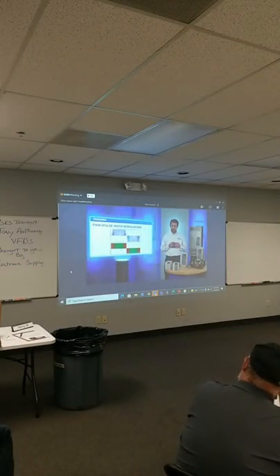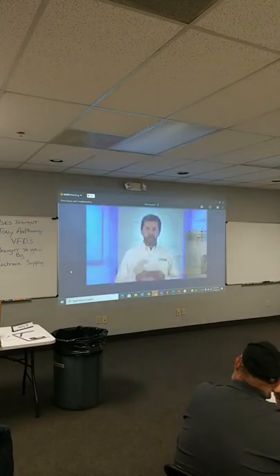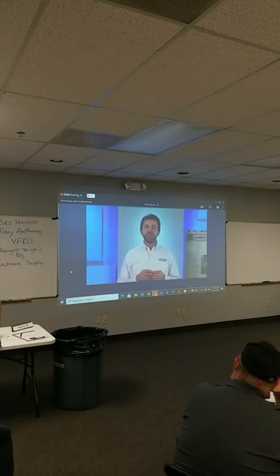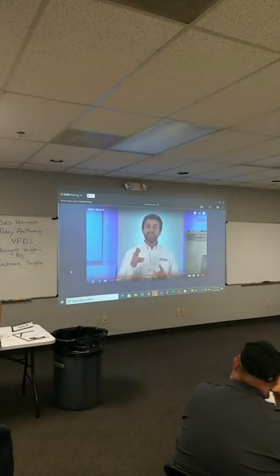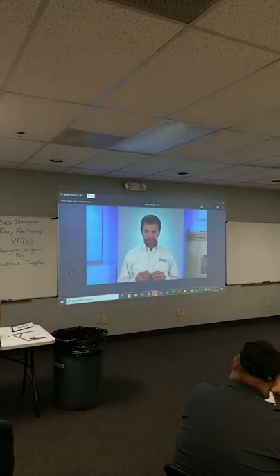You will notice that the voltage waveform is almost square, but is happening in the positive and negative regions. That's because the IGBTs are pulling from a constant DC bus. Voltage reacts very quickly compared to current, which causes this block-type output. The pulses are high in amplitude, but the RMS, or root mean square, voltage appears equivalent to the motor-rated voltage. You will find motors that can handle this PWM-style waveform tend to be labeled inverter duty on the nameplate.